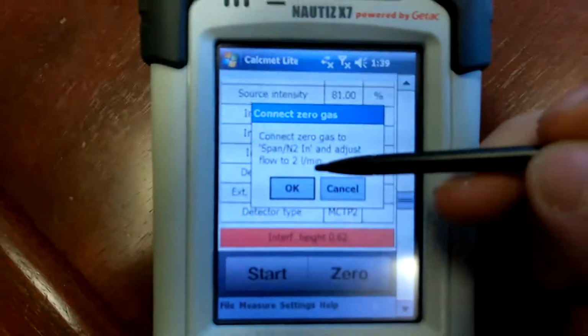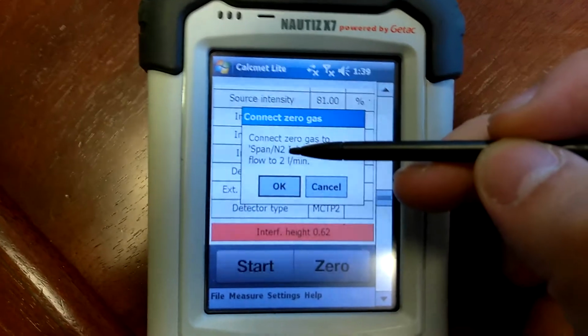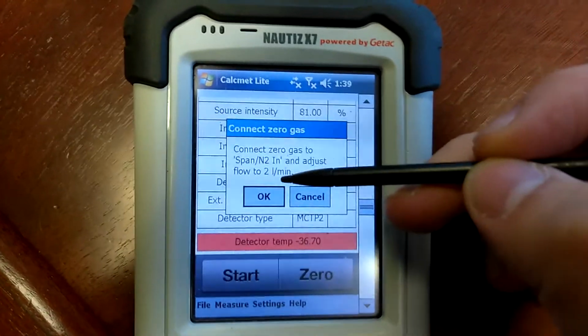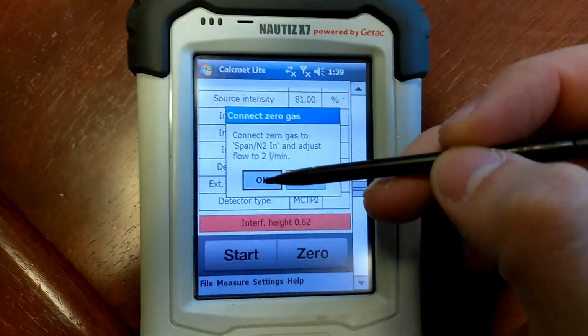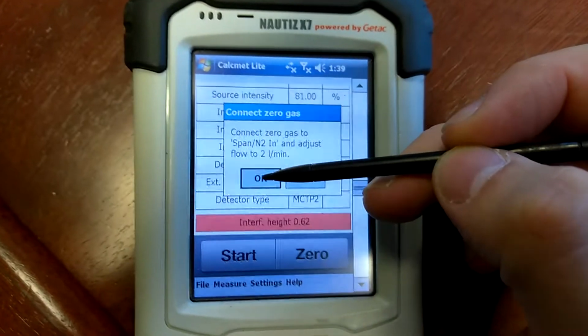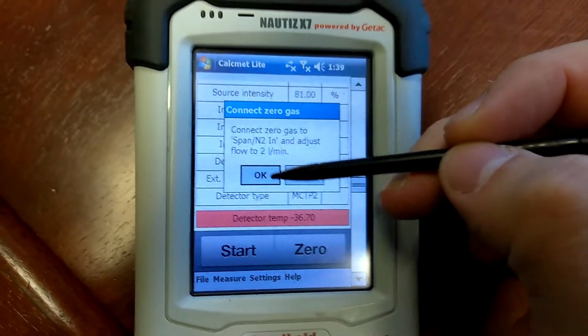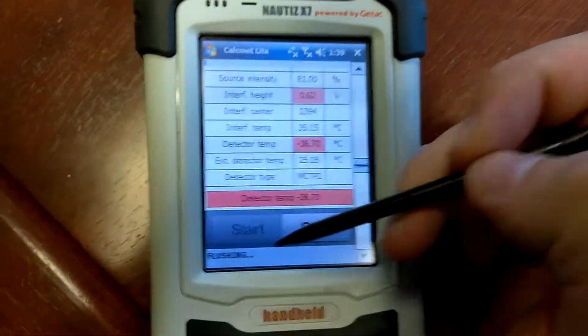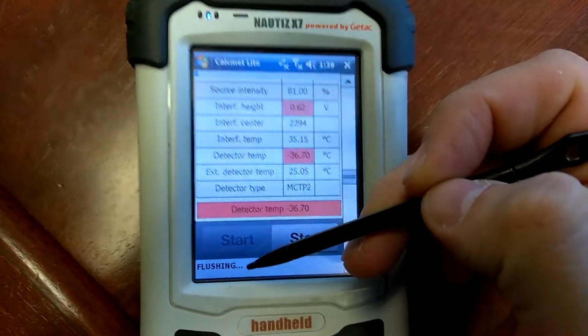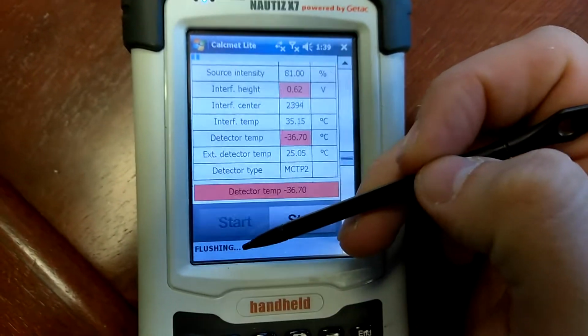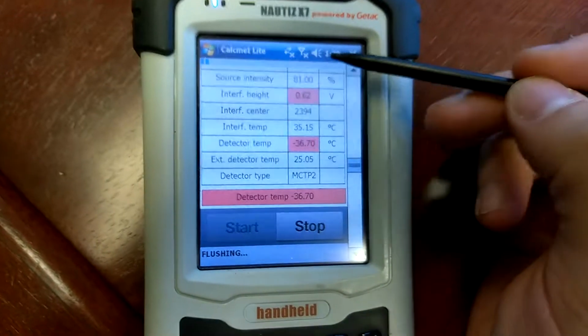It will give us a confirmation dialog. Span N2. We want to make sure we've got nitrogen. 2 liters per minute. Again, 1 I've been told is okay. 6 is too high. 3 probably okay as well. Go ahead and hit OK. Now this is going to take about 5 minutes to complete. It'll say flushing, and then it'll say measuring while this blue bar builds.